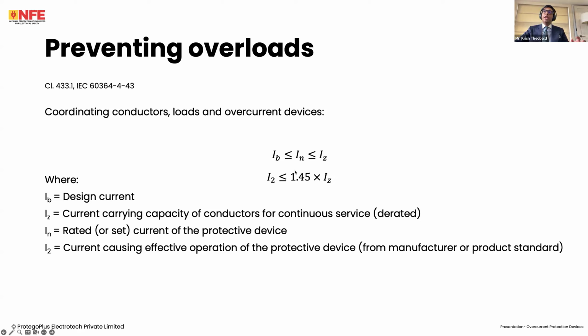We, as electrical installation designers, need to ensure that this value of I2 does not exceed 1.45 times IZ. So it does not exceed 1.45 times the derated current carrying capacity. Very important thing to take into mind. I'll show you a little later what that means. And just so you know, for an MCB, a 60898 MCB, I2 is 1.45 times IN. So if this equation is satisfied, that equation by default gets satisfied. However, when you use devices like HRC fuses or rewirable fuses, that's when we start to see problems with this equation. And I'll show you how to deal with it.